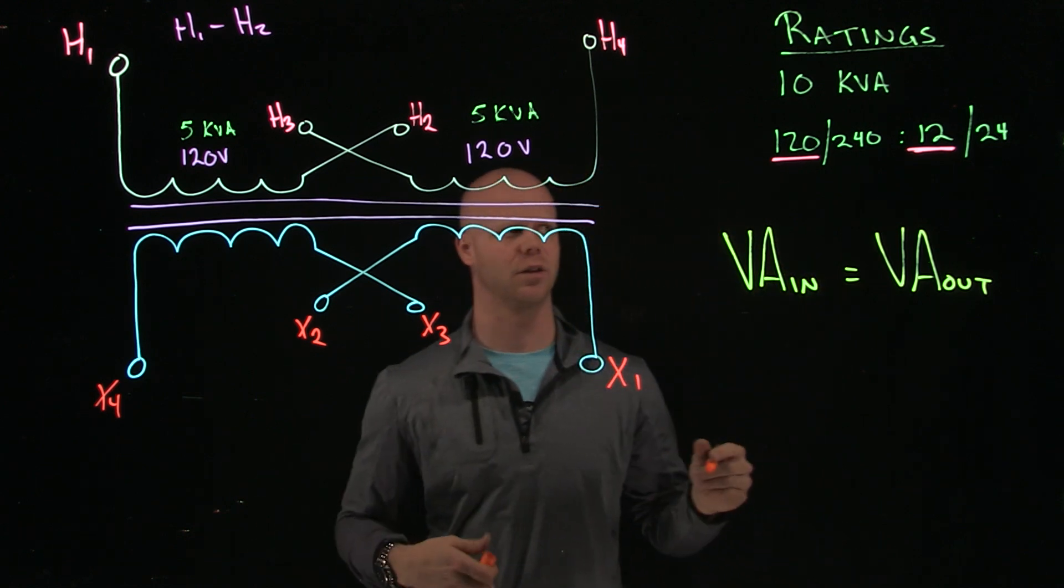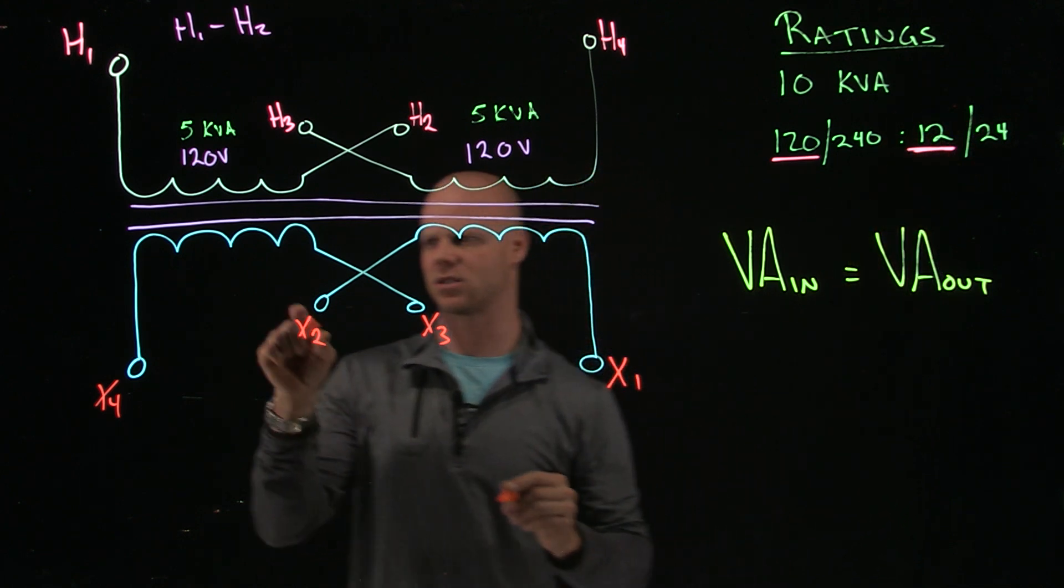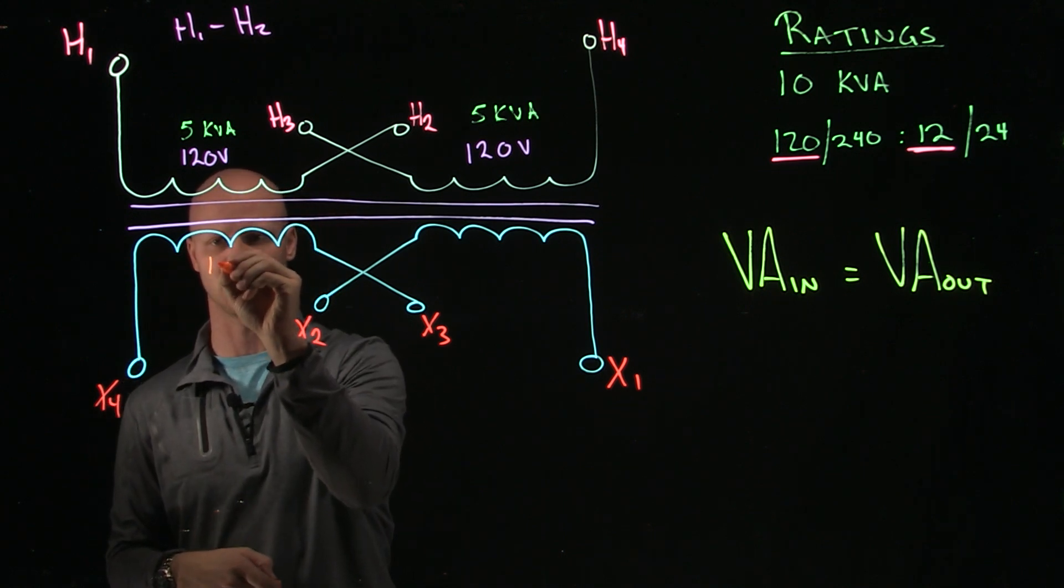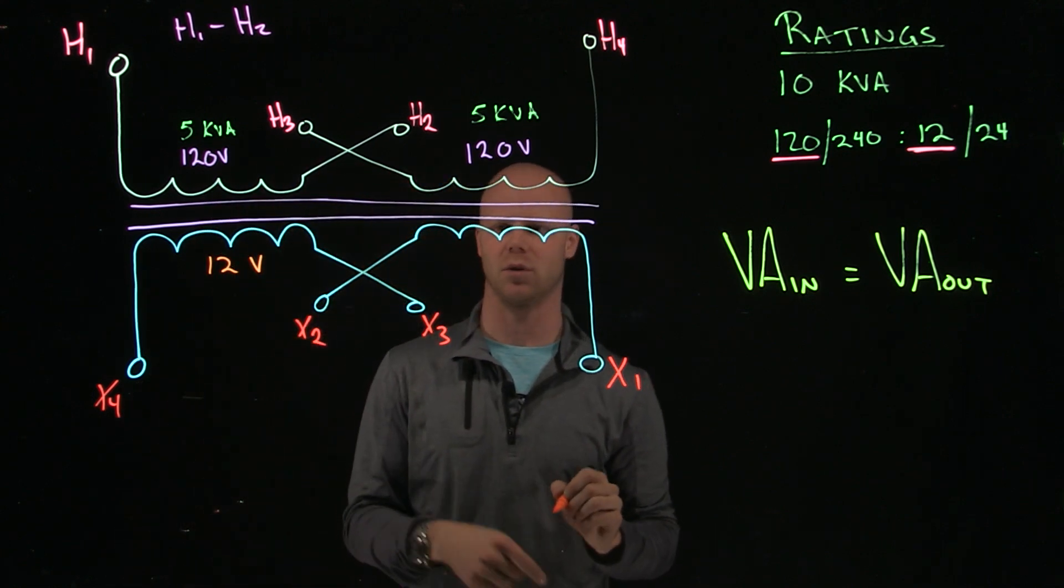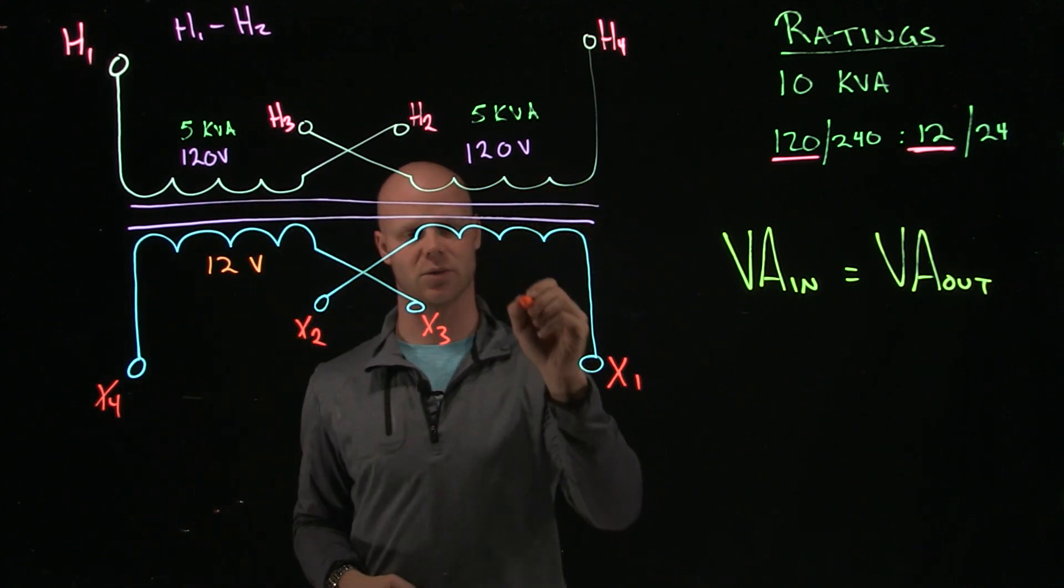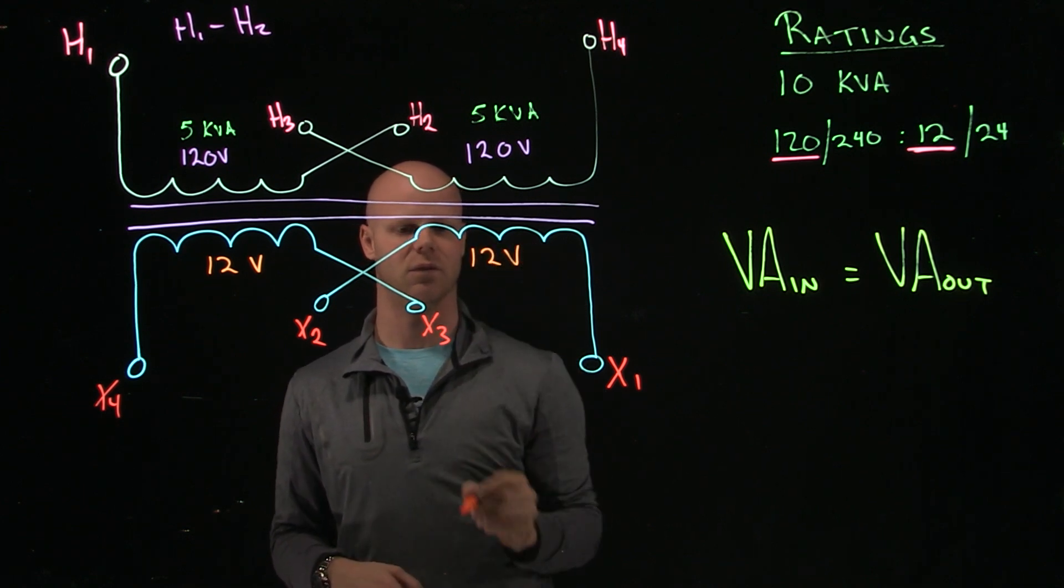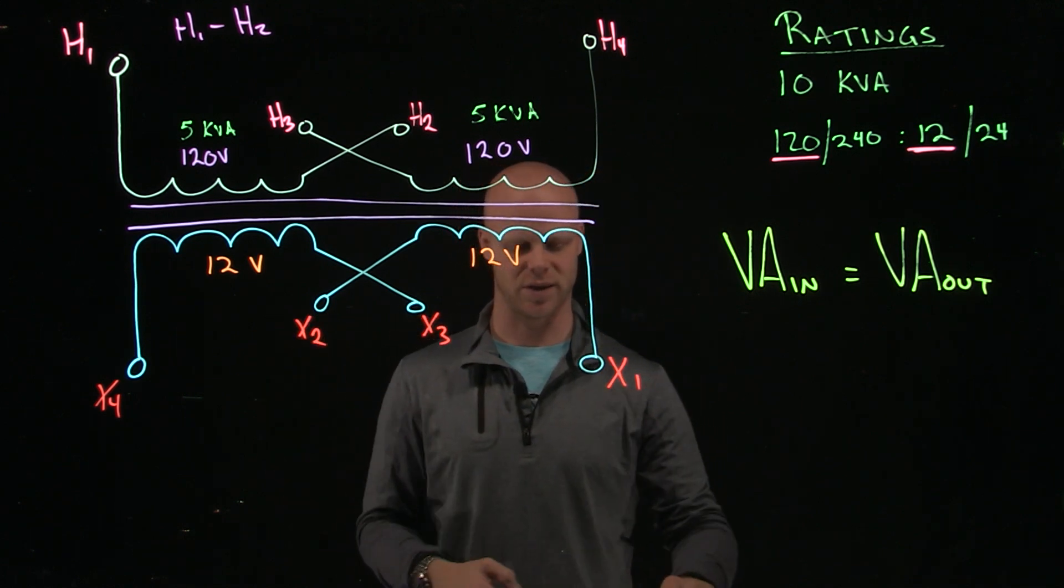Secondary side, we're going to follow that exact same principle. This lower voltage on that multiple rating is going to be the rating of one of these windings. So this one winding will have a 12 volt rating. This winding is going to be physically identical, electrically identical. This will have a 12 volt rating. I can have a choice. I can wire these in series. I can wire them in parallel.